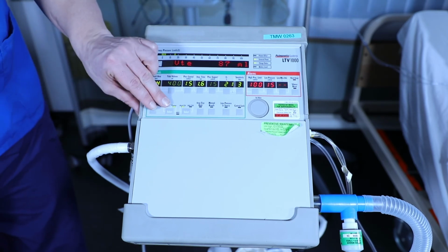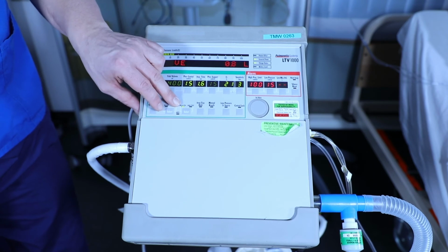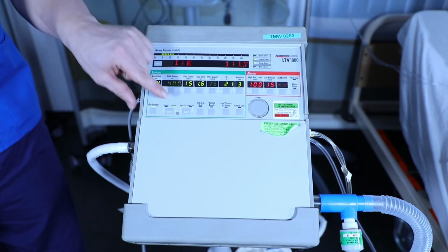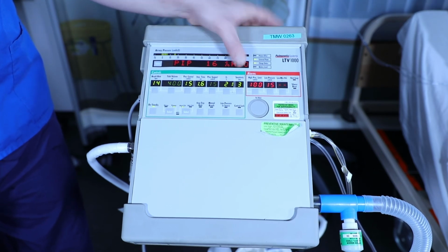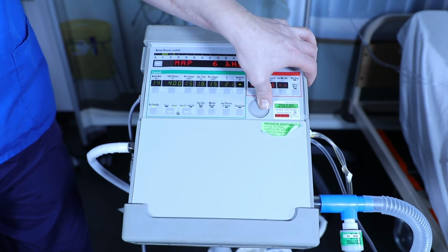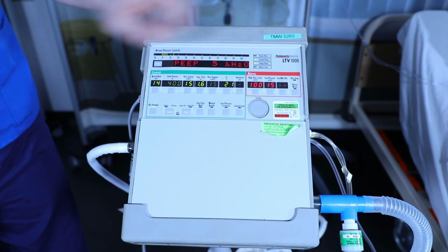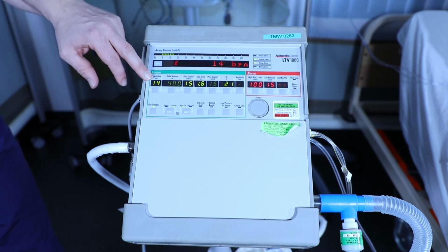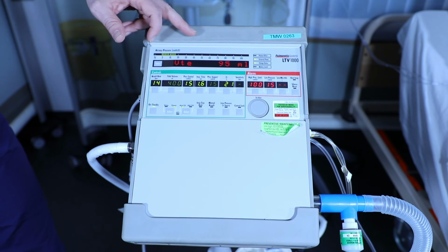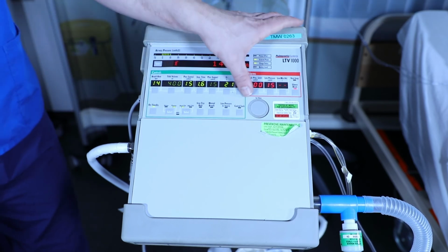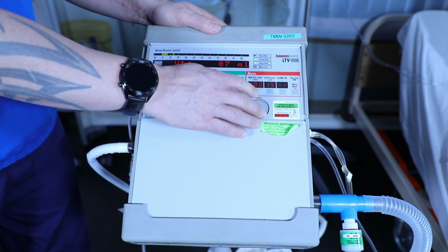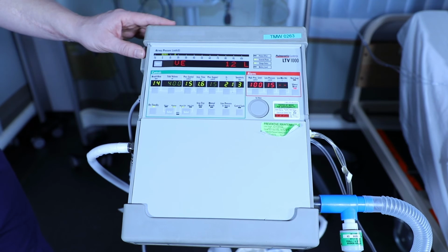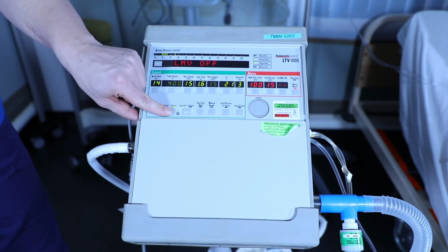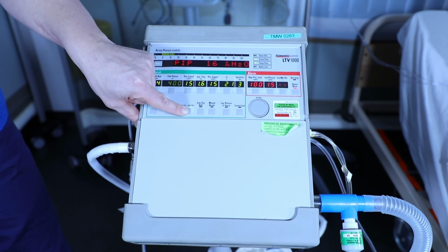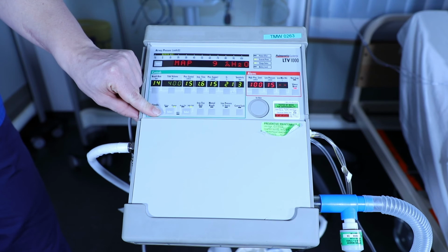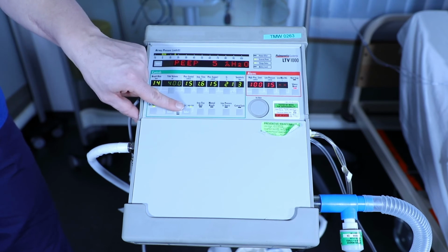As we can see here, we're currently in pressure assist control. Now, if the patient was sufficiently awake, they would be able to trigger breaths because we've got the sensitivity set to 3 litres per minute. If we switch this off by rotating the dial to the dash, then the patient will only receive mandatory breaths at a rate of 14 per minute with a pressure control of 15 with the PEEP set at 5 or 6. If we turn this back on, we can change between assist control to SIMV CPAP, to go into full CPAP mode without any pressure support.